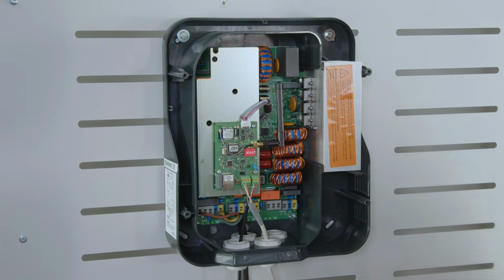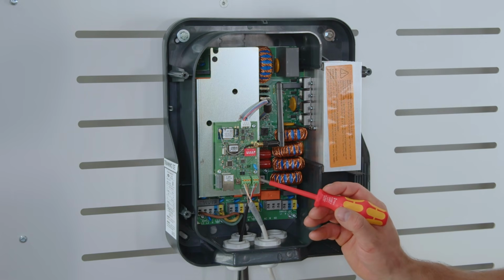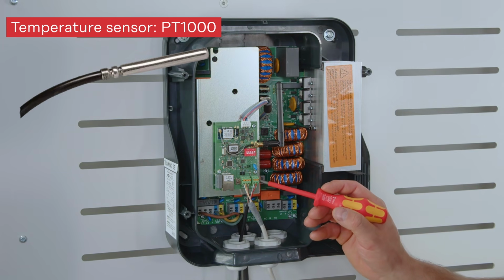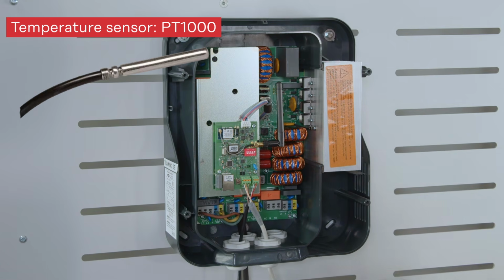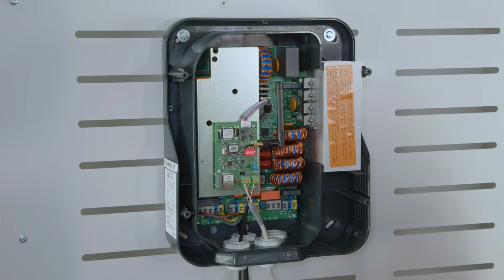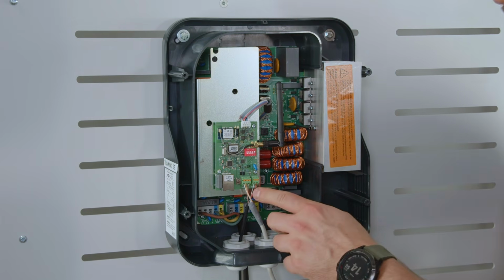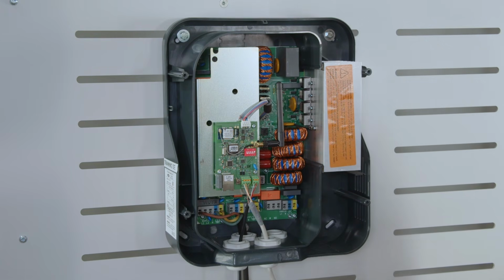All right, last but not least, we also find ourselves here with a PT1000, a temperature sensor. And this one can be equipped optionally, so you don't have to use it, but again, I can highly recommend it because it allows us a few more features, which I will show you later on in the commissioning. So this would be very standard here connected, and then we would set it within our boiler in order to measure correctly. This would actually be one of the big benefits.